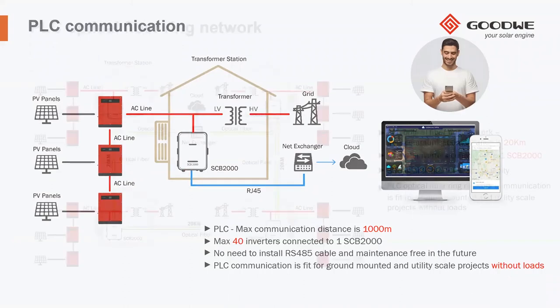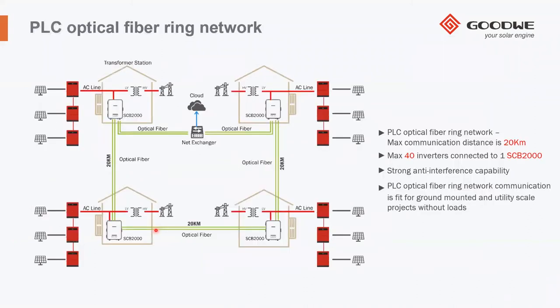Another possibility for communication is the case where you have several plants, not in the same location but quite close to each other. In this case, you can use optical fiber for communication up to 20 kilometers, extremely fast and extremely reliable. Again, you can use the power line data monitoring transfer to the SCB2000. The SCB2000 can be used to connect via optical fiber all four plants, like in this example, and send the communication data to the net exchanger and then to the cloud. The maximum communication distance is 20 kilometers, and you can connect up to 40 inverters to one SCB2000 box.